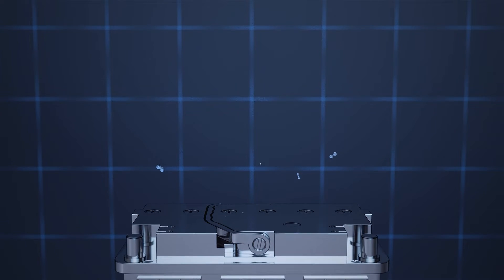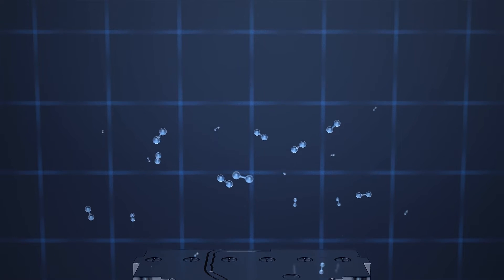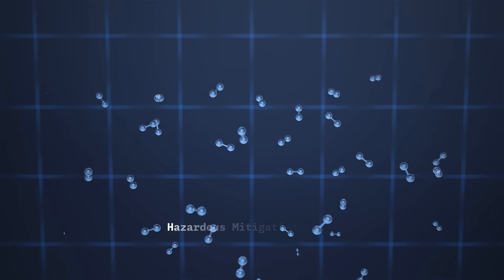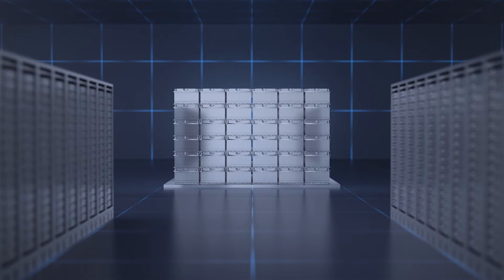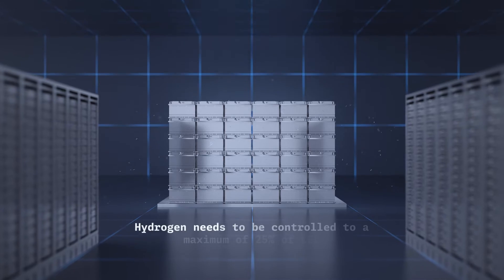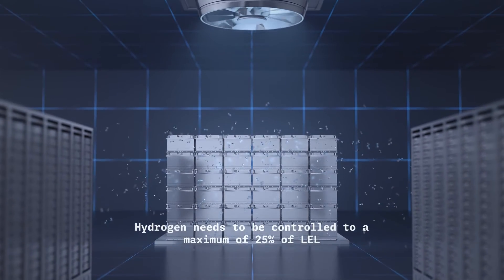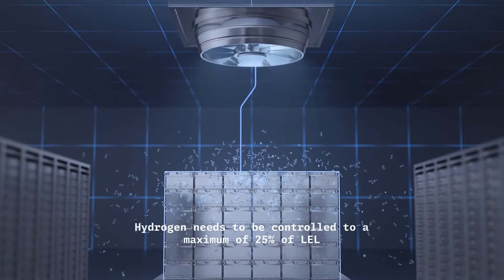To manage this hydrogen venting, battery room operators develop comprehensive hazardous mitigation plans to control hydrogen to a maximum concentration of 25% of the lower explosion limit, abbreviated as LEL.